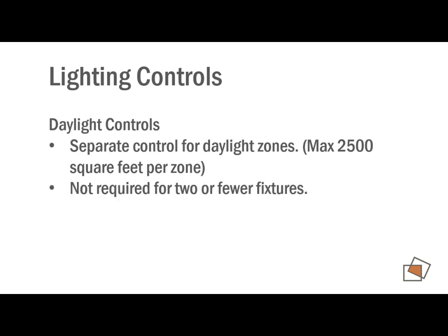But there's a couple exceptions. So this would be like an office, right? Two or fewer fixtures, you don't have to have a separate daylight control for that. And then it also says this can be manual or automatic controls. A lot of times automatic is probably the easier way to do it. You put a photocell in that area, and then you wire it to those fixtures, and then it just dims down based on the input from that photocell, but it also could just be a dimmer switch on the wall.